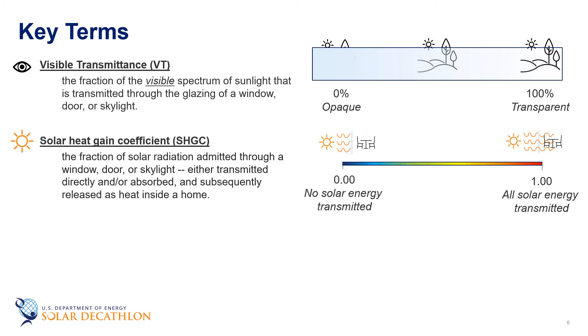Solar heat gain coefficient is another closely related term, except it incorporates the entire electromagnetic spectrum and not just the visible portion. It represents the amount of solar energy that enters through the window compared to the amount that would have entered if there was nothing between you and the sun. For example, a window with a solar heat gain coefficient of 0.25 only allows one quarter of the sun's heat to enter the space.